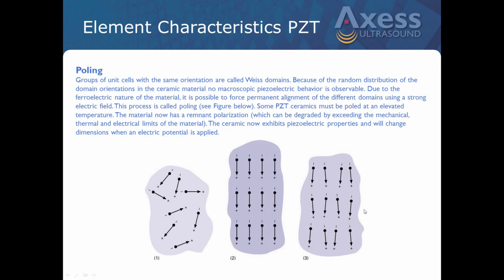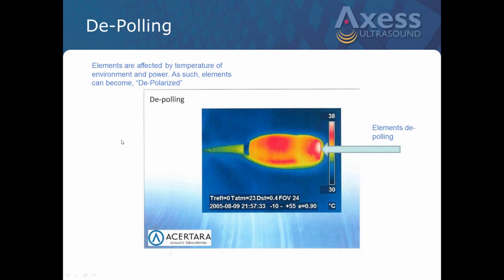So figure 2 here shows a properly aligned PZT array that's poled at the correct levels. Figure 3 would be representative of a PZT array that has come unpoled. As you can see, some of the elements are starting to get out of alignment. That can happen, and I'll talk later in the presentation about that, through extreme heat or electrical power that's out of spec to the probe, and so on. So there are issues where arrays can just become depoled, when in fact the array is good, but you have to be able to repole it back into position like figure 2.